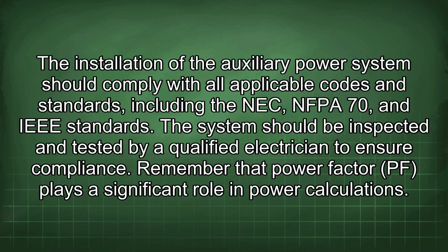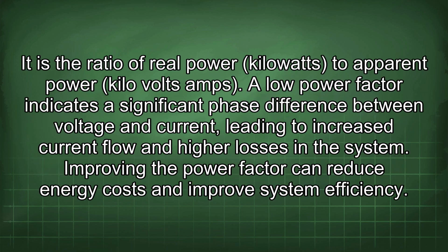Remember that power factor (PF) plays a significant role in power calculations. It is the ratio of real power (kilowatts) to apparent power (kilovolt-amps). A low power factor indicates a significant phase difference between voltage and current, leading to increased current flow and higher losses in the system. Improving the power factor can reduce energy costs and improve system efficiency.